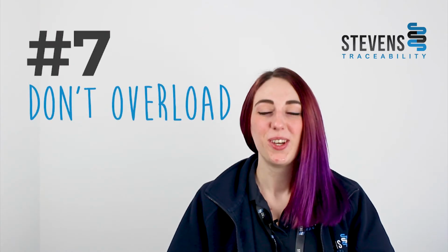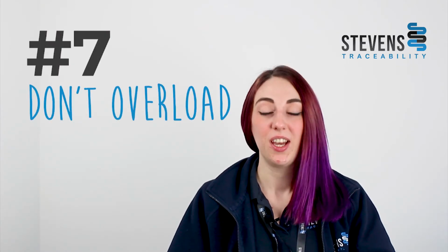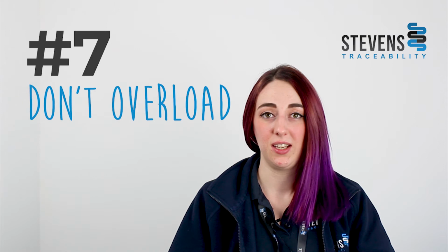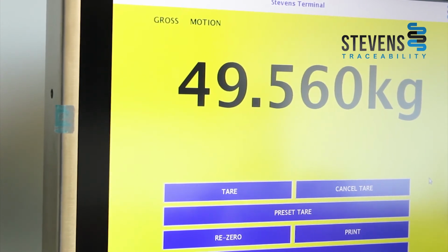Tip number 7, don't overload your scale. Your scale has a set capacity. You should not overload this capacity. This could cause major damage to the load cell, including twisting or bending the load cell, which will mean it will need a complete replacement.